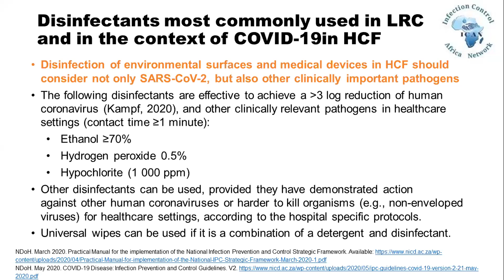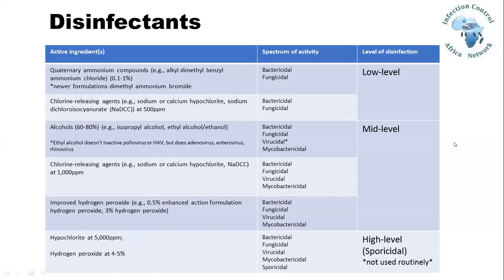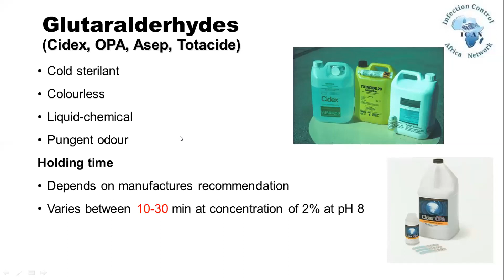Here's also another table that just lists some disinfectants for you, looking at the active ingredient, the spectrum of activity, and then the level of disinfection. So you can put those tables next to one another, and then you can decide on the correct disinfectant for the correct item that you are wanting to clean. We look at glutaraldehydes, which are well used over the world. We do know that the contact time can be between 10 and 30 minutes, depending on the concentration. And we do know that the glutaraldehydes have a pungent odor and the fumes can be quite toxic to the staff member. So they do then use the OPA or the Cidex OPA solutions and not the heavy concentrations.